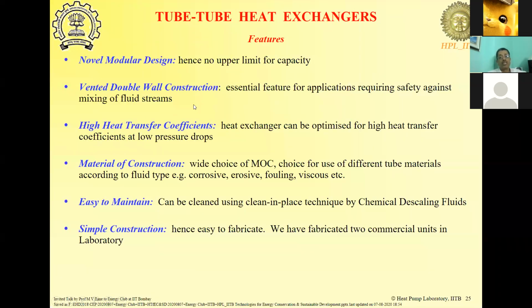So they are modular in nature, they are vented double walls, so they are very reliable. They don't allow mixing to happen. So they can offer high heat transfer coefficient because of the bends and mixing that happens within the boundary layer because of the structure of the heat exchanger. You have a wide choice of material of construction. You can select the tube material based on the fluid that is passing through it and need not be compatible with both the fluids. And cleaning can be done in place without having to open it, unlike plate heat exchangers, which can get fouled and then you have to open them up.